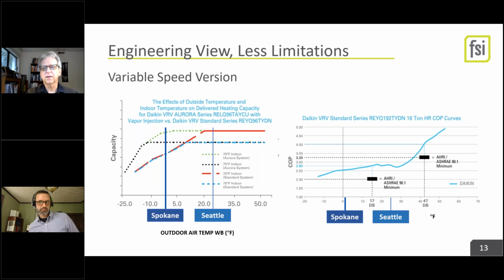And what's weird to me on that particular graph on the right is that from like -5 up to 30, there's really not much change in the COP. Yeah. And then it really takes off as you get into warmer temperatures, but it's pretty consistent down there. It is, yeah, and the COP being up at 4, 4.5, 5 at the temperatures we have a lot of the time in Seattle, it's not rare. If you look at our bin data, living in that 35, 40, 45, 50 range, we've got a lot of hours in that range. So there's an efficiency bump. This is specific to this Daikin system, but you do see more or less that trend. The warmer it gets, the more heat you can pull out of the air easier, and it tails off down to its limiting temperature, and that's really refrigerant based. So the refrigerant can only go so low before you stop being able to get heat.